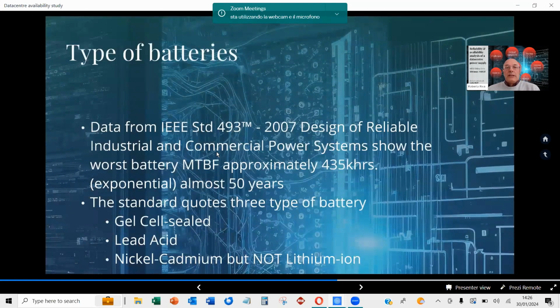Unfortunately, our data source, the IEEE 493, did not have lithium batteries. We looked at modeling with the worst battery, but that had a mean life of something like 50 years, or 435,000 hours. There are 3 types, and that was the worst one, but we knew we couldn't really use something like that. We wanted something more realistic. The standard supports 3 types of battery: the gel cell sealed battery, the lead acid, and the nickel cadmium, but not the lithium.